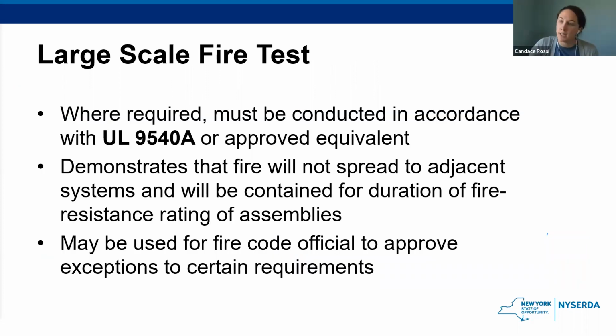So in addition to the hazard mitigation analysis, there's also a requirement for large scale fire testing. So where required, large scale fire testing must be conducted on a representative energy storage system in accordance with UL 9540A or an approved equivalent by an approved testing laboratory. So the test must show that a fire involving one system will not propagate to the adjacent system. Most of the design requirements for energy storage is to ensure that if there is an incident or fire, it does not spread to a neighboring cell, module, or rack. It should also show that if a fire does occur, it will be contained within the area for the duration of the fire resistant rating of the room assemblies. So this test report must be provided to the fire code official for review and approval. There are a few requirements throughout the supplement that can be altered based on the results of a large scale fire testing, which we'll touch on as we go through this.